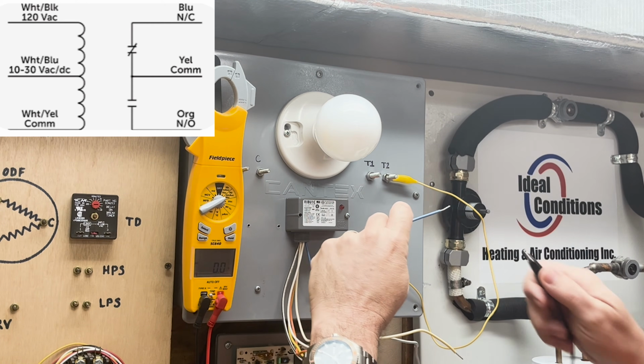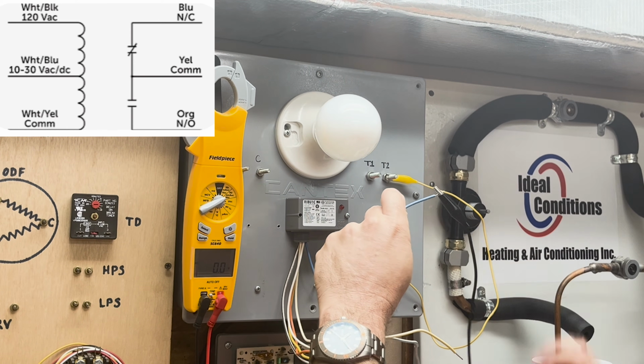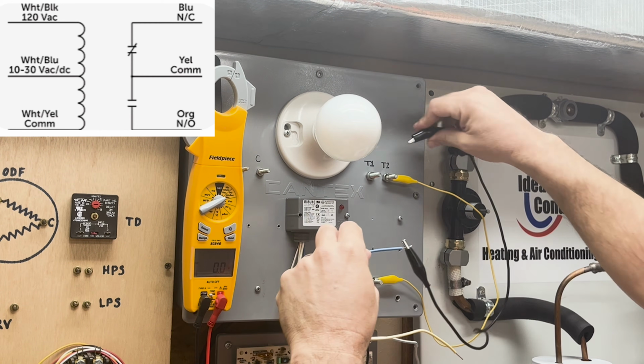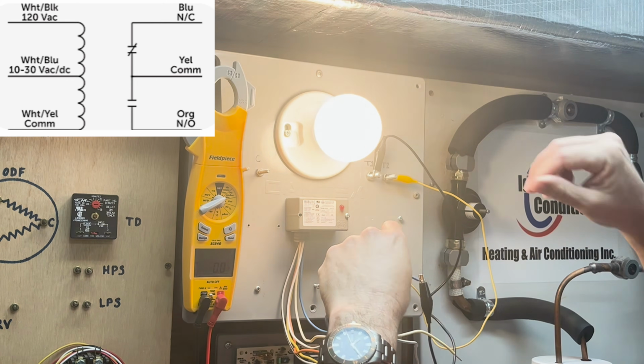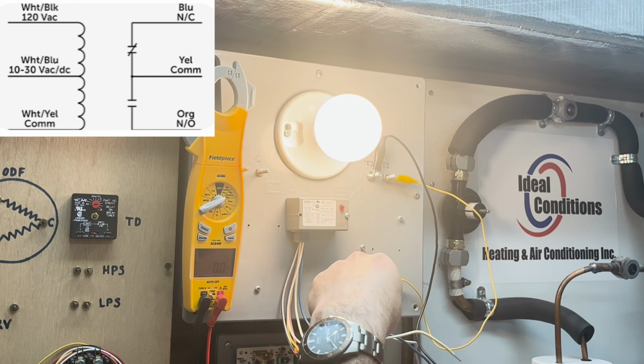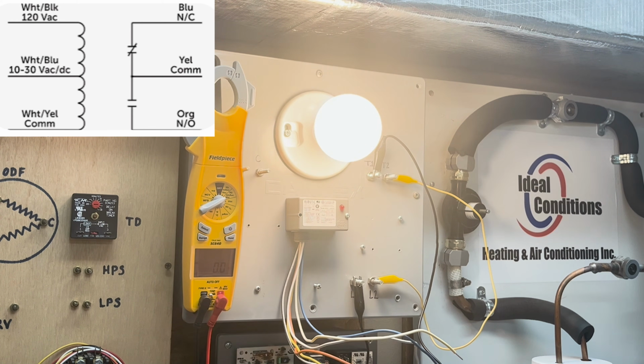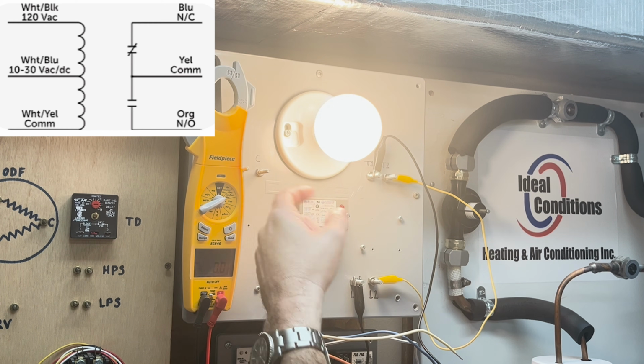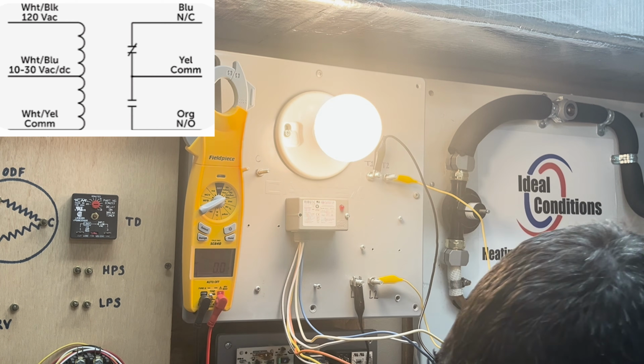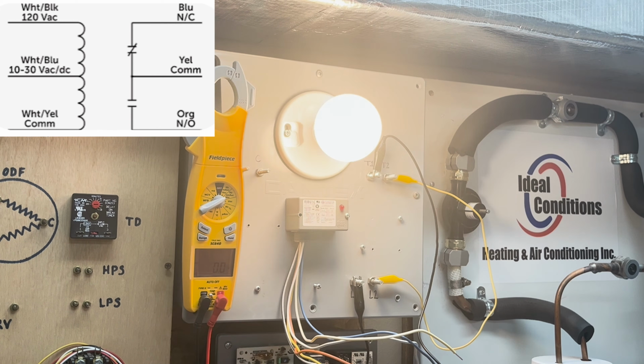All right, so now I'm going to go ahead and connect power there, and we're going to come back and connect that to T1. If I wanted to connect this to my normally closed, the load would always be energized, and when I apply coil voltage, the load will drop out. So we're going to go ahead and apply coil voltage.